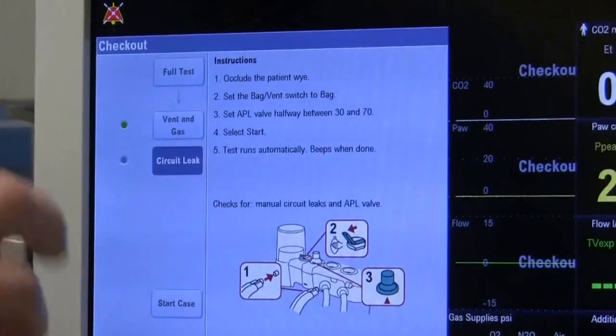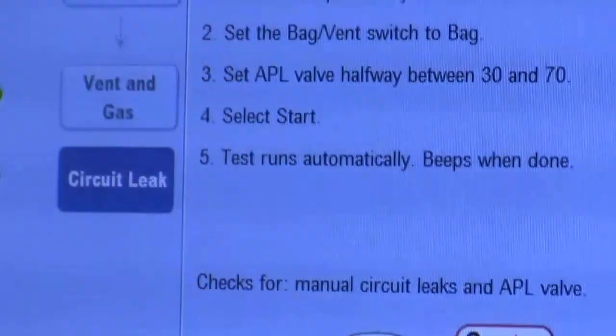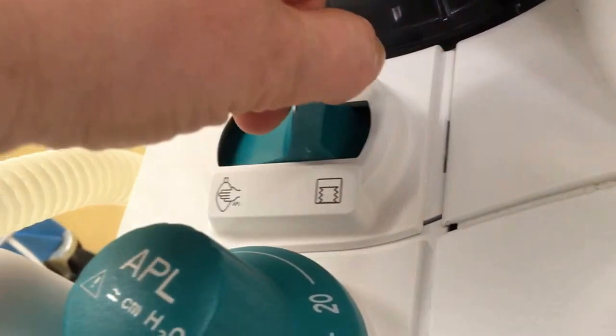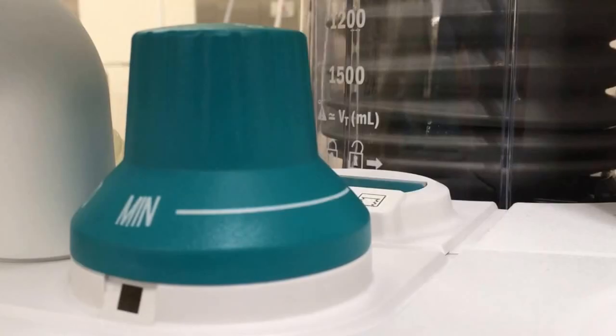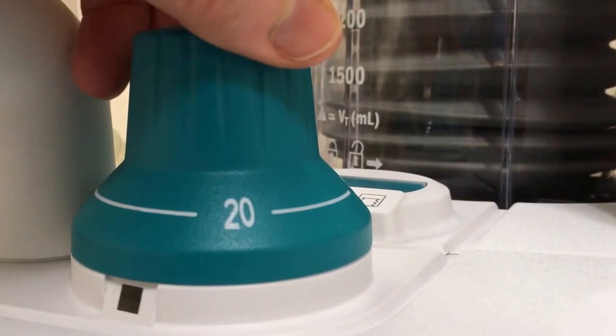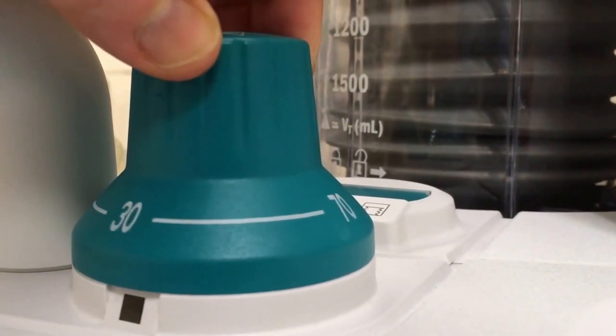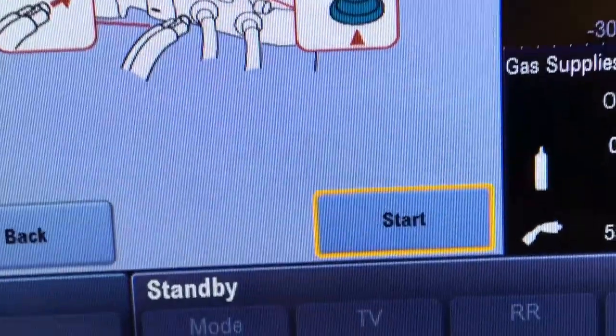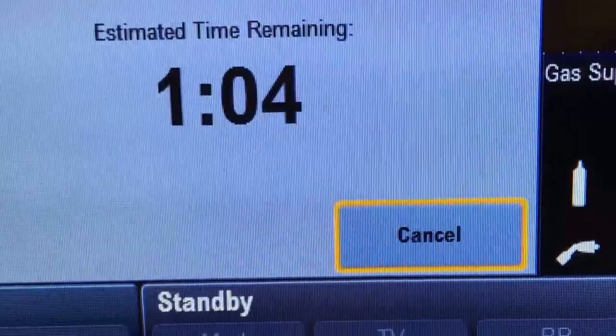Now we're going to do the circuit leak. So we're going to occlude the Y, switch your bag vent switch over to bag, put your APL valve between 30 and 70, and select start. And this is going to be doing your circuit leak.